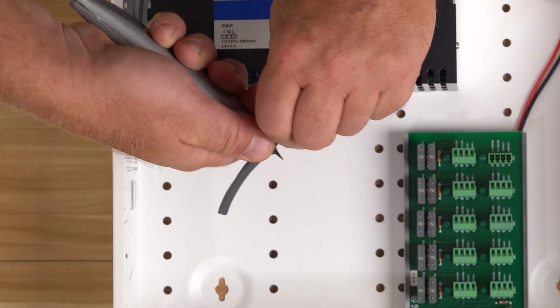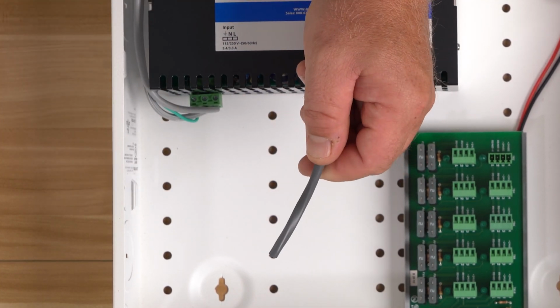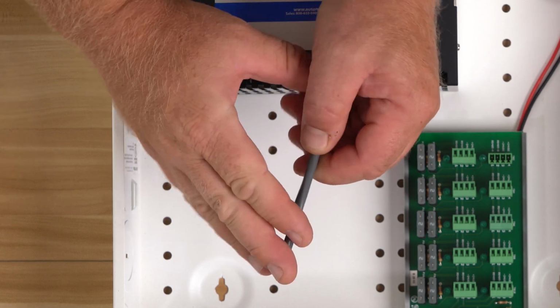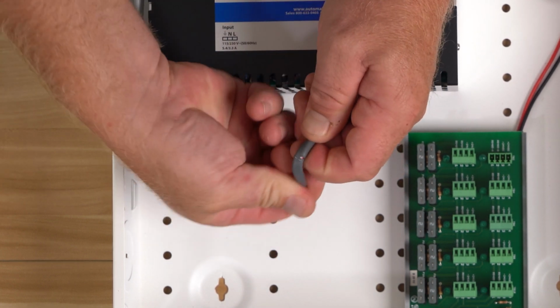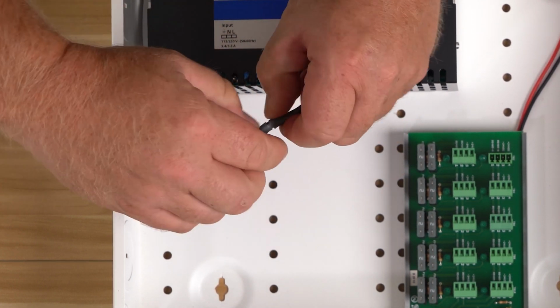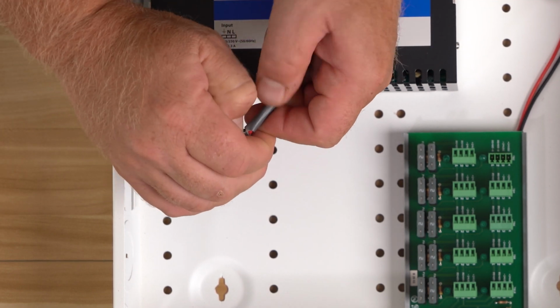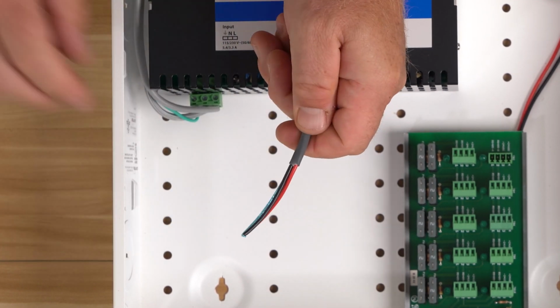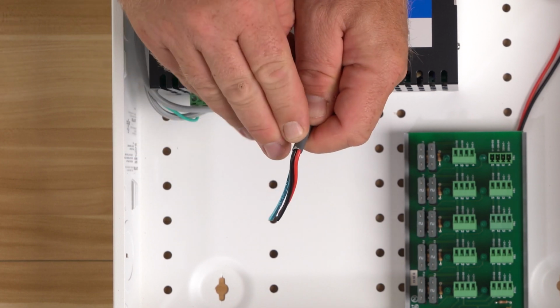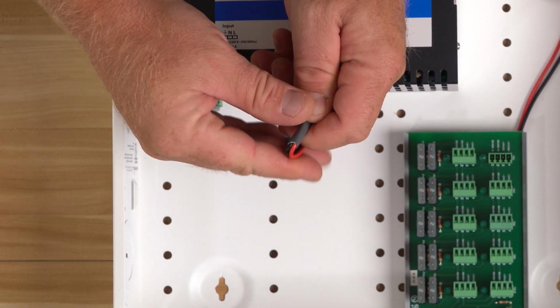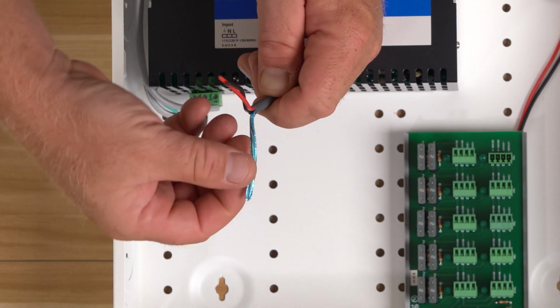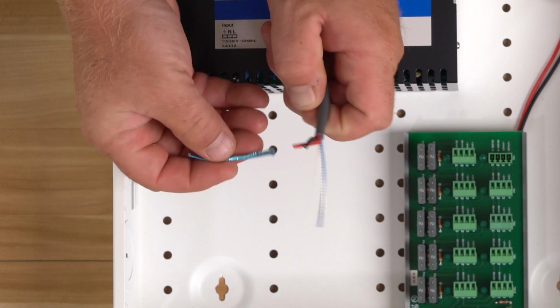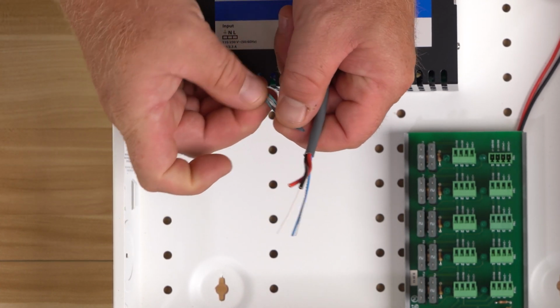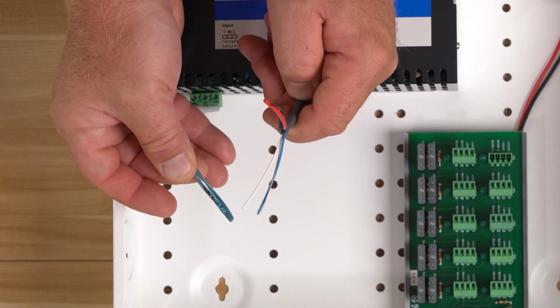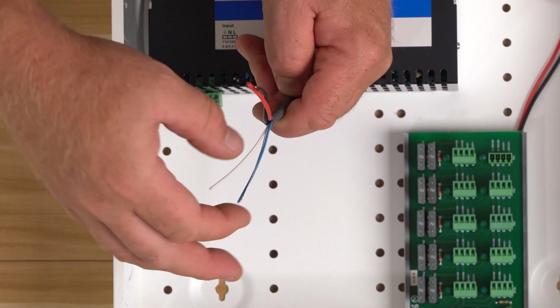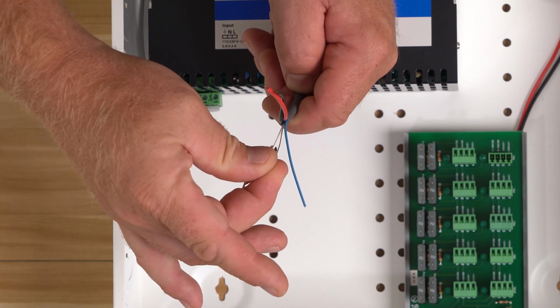Go ahead and strip off the jacket. Now, very, very lightly, you don't want to put a big indent on this, cutting through the cable on the inside. Once you remove your jacket, you want to check your positive and negative, which is black and red. Make sure that you didn't go and cut those down to the copper. And then on the opposing side, you've got your shield, which keeps any noise off of the line. And then you've got your RS-485 and then your drain.